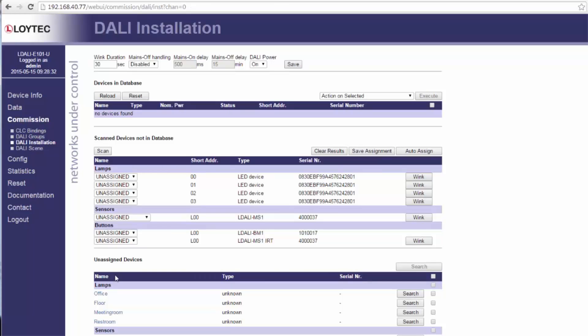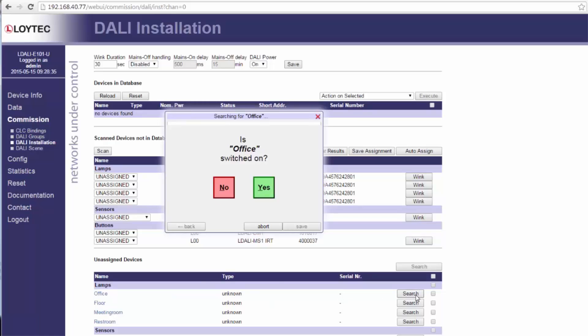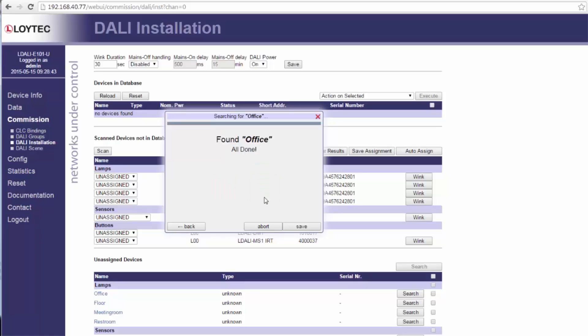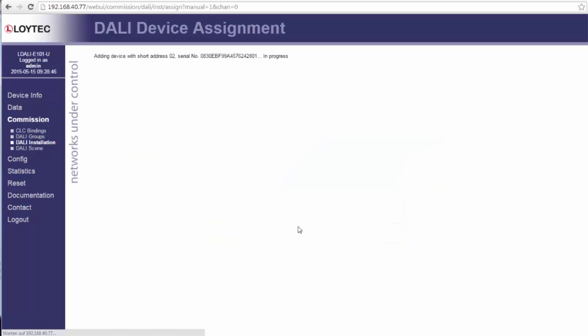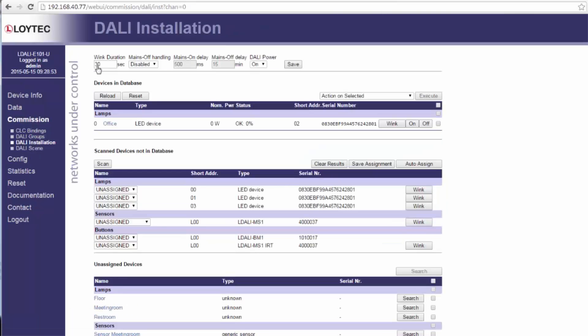Using the search button the DALI wizard switches on one half of the ballasts and asks if the desired device is on. Is it not the case press no and DALI will switch on the half of the remaining lights and ask again whether the requested lamp is burning or not. This routine will be repeated till the desired ballast is found. So this binary search will find the correct ballast in a full used DALI channel within a maximum of 6 steps.